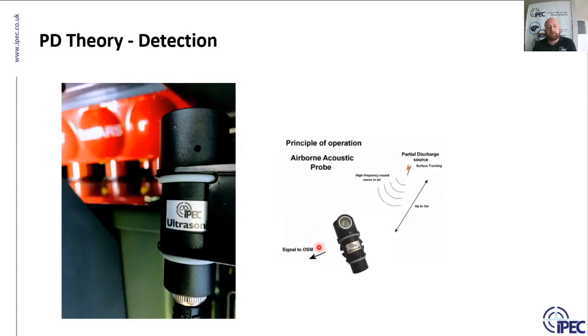The next one then is the ultrasonic sensor. Ultrasonic detection on switchgear is very simple. It's a 40 kilohertz microphone, one of the most simple sensors that you can make. Also, the interpretation and the detection of the signal is very simple. Quite often you use them built into the head of handheld instruments, put some headphones on and point at where there may be some surface tracking occurring. If surface tracking does occur, the sensor is very, very sensitive and will very easily pick up that signal.